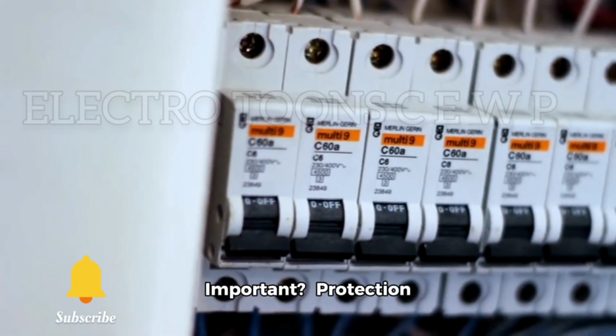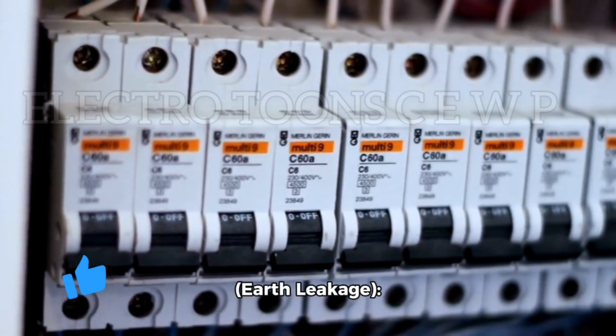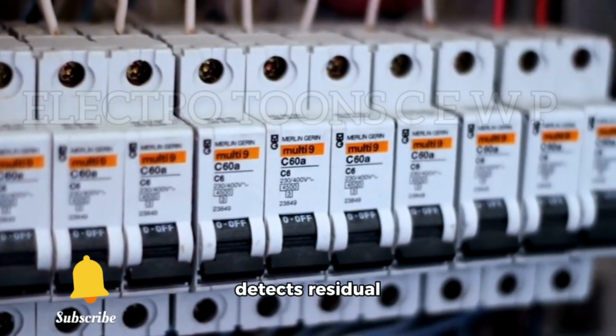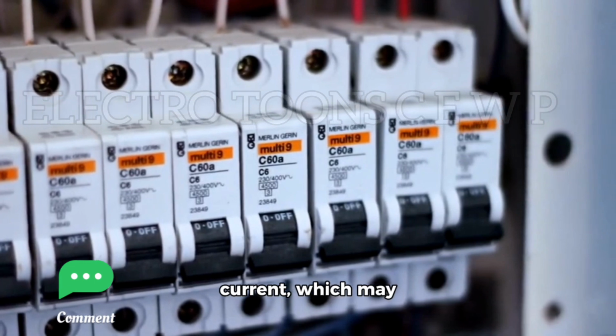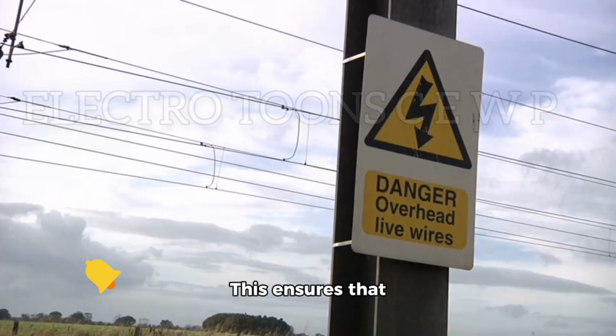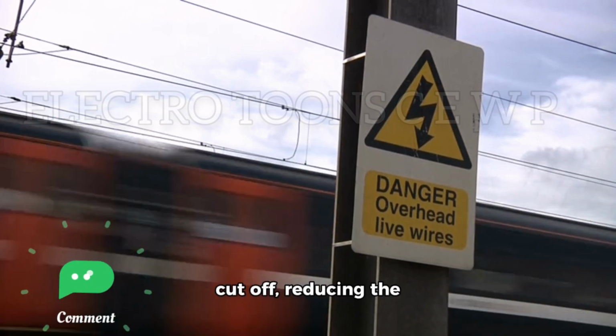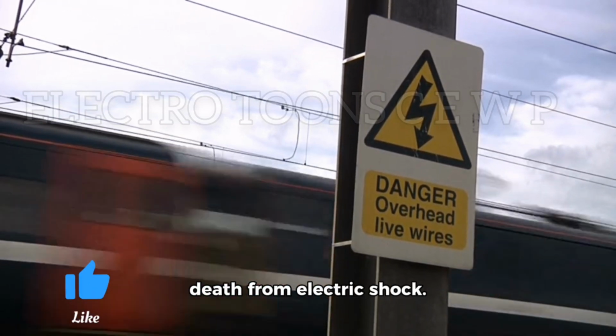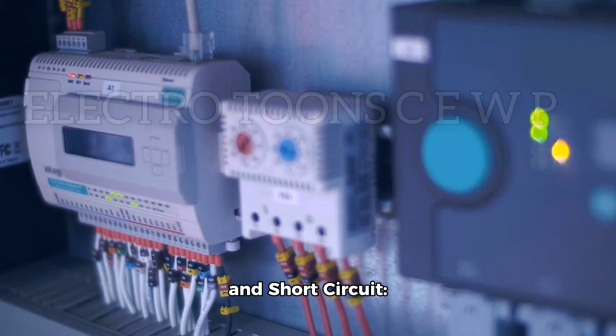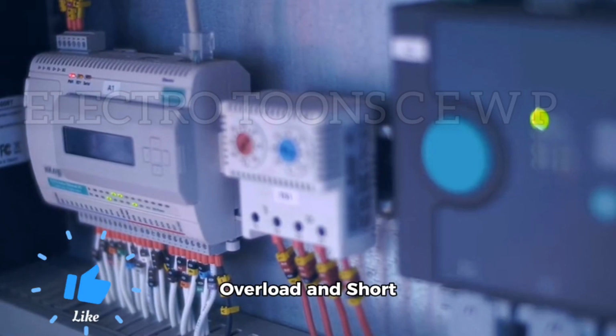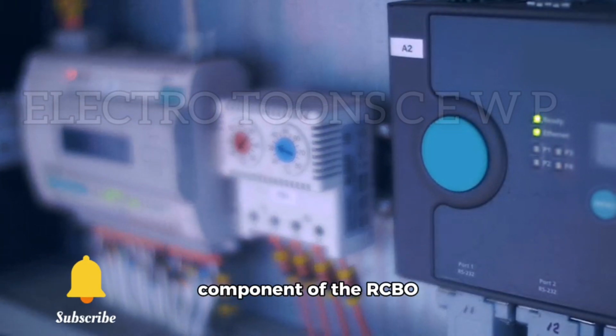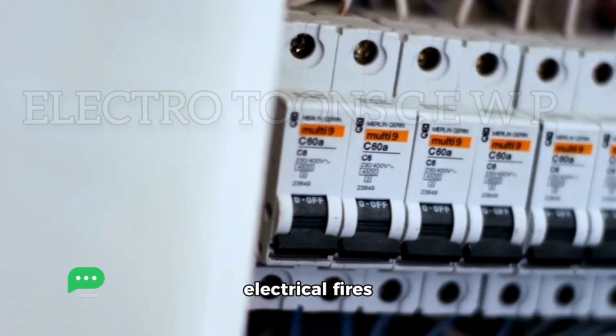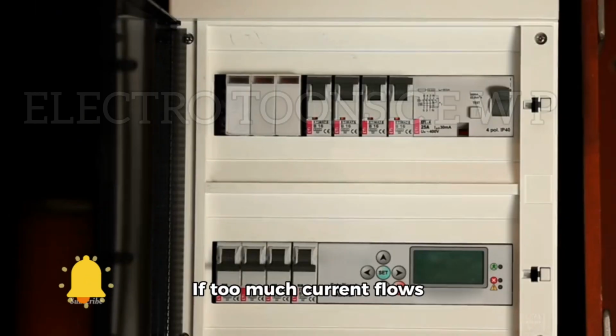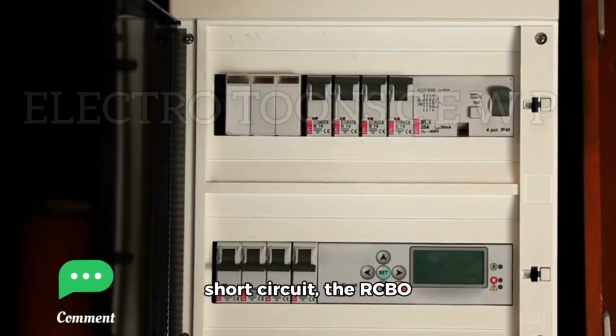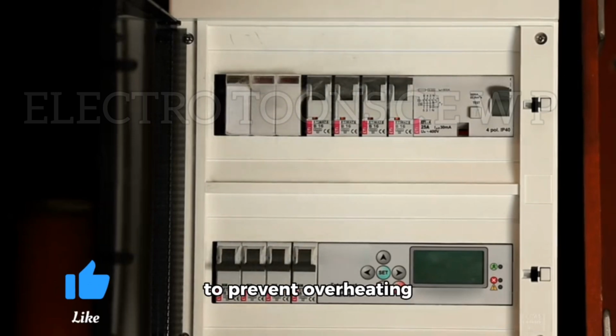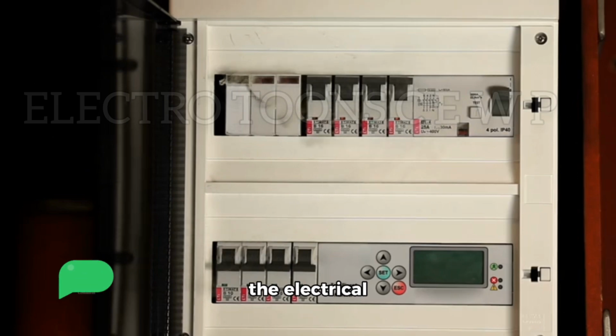Why is an RCBO important? Protection against electric shock, earth leakage. The RCBO's RCD feature detects residual current or leakage current, which may occur when an individual is electrocuted. This ensures that electricity is quickly cut off, reducing the chances of injury or death from electric shock. Protection against overload and short circuit. The overload protection component of the RCBO safeguards against electrical fires caused by excessive current. If too much current flows due to an overload or short circuit, the RCBO disconnects the circuit to prevent overheating and potential damage to the electrical installation or devices.